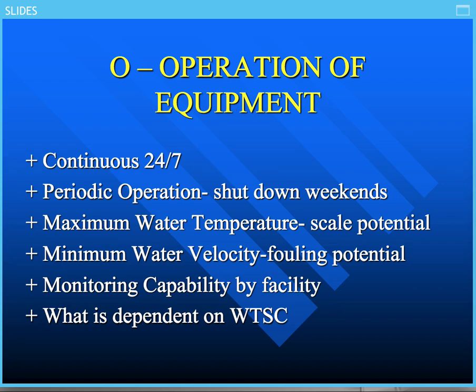Then, the other question is whether the facility is capable of actually monitoring the water treatment chemical programs. A major industry will normally have somebody on staff or a water treatment service company providing that type of service. An air conditioning type system, on the other hand, may not have any capability on the staff and only has periodic testing of the water, like once a week or sometimes once a month. That is not very sufficient. You have to have much better control than that.